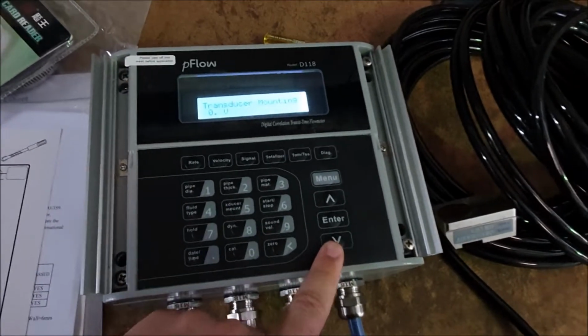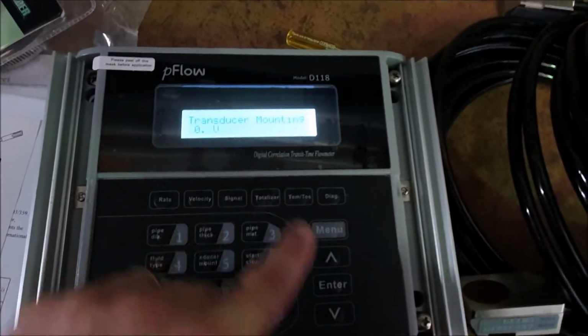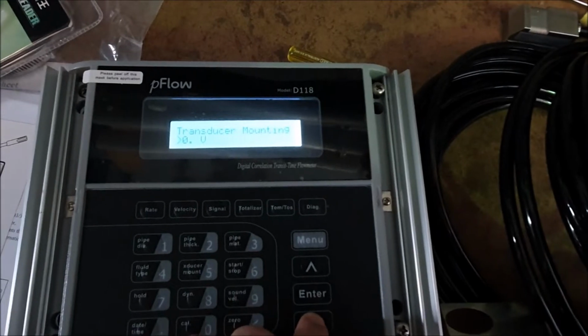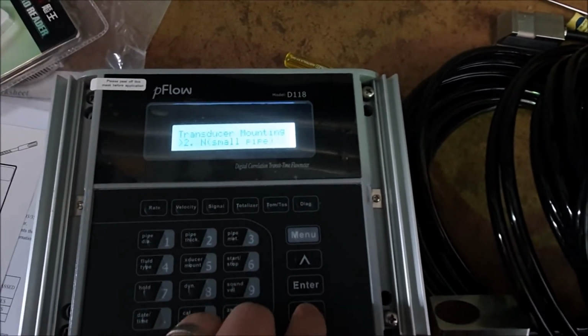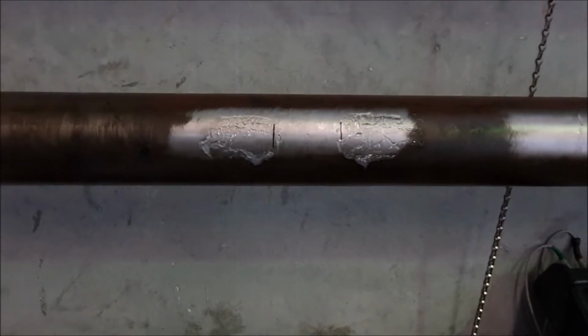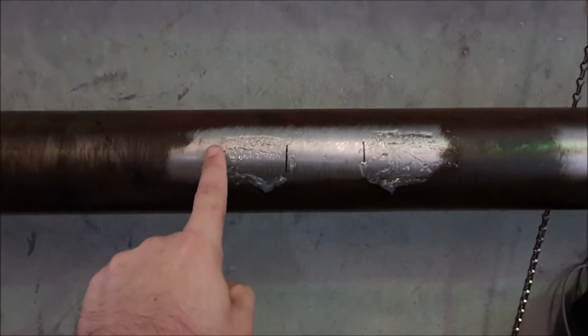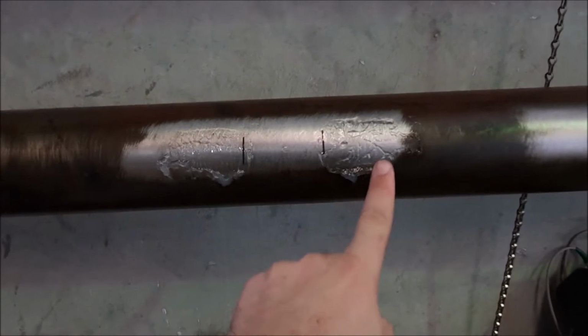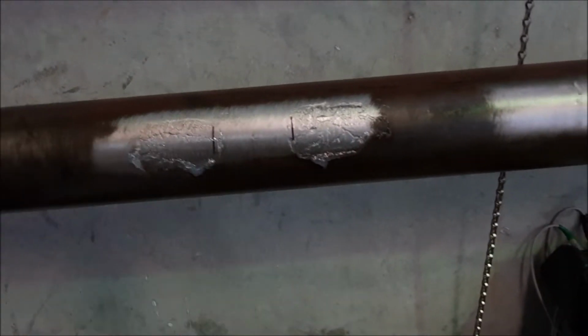Transducer mounting, you'll see it's set to V. V is the most common, considered the standard method, but there's also Z and N you can choose from. In V format, the signal will bounce from one transducer off the back of the pipe and into the other. That's the most common, that's what we're doing here today, but you might need to try one of the other methods if needed.